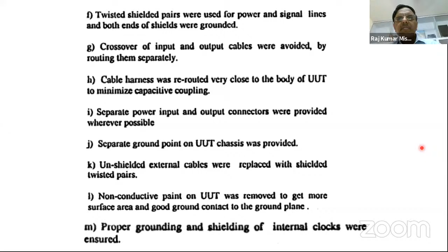Again, a very important thing: unshielded external cables were replaced by shielded twisted pairs. Non-conductive paint on the EUT was removed to get more surface area and good ground contact to the ground plane. Proper grounding and shielding of internal clocks was ensured.